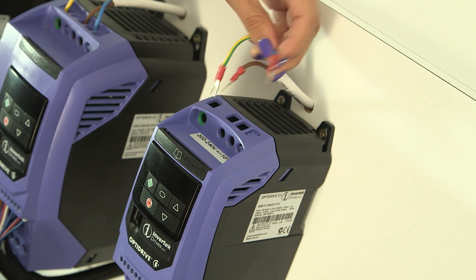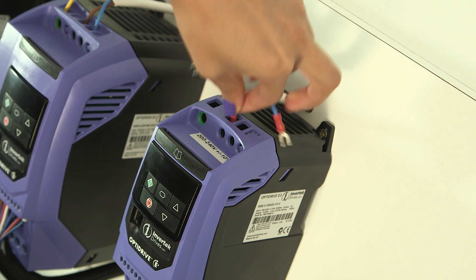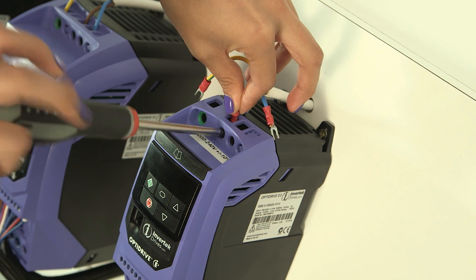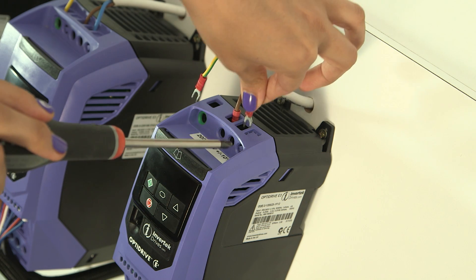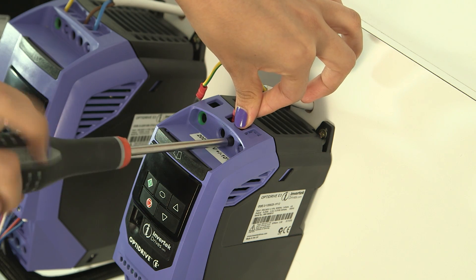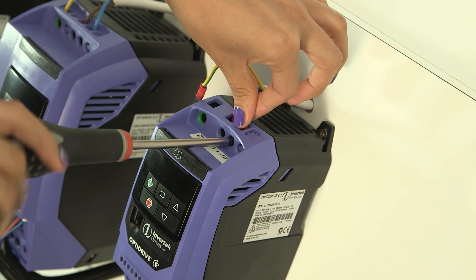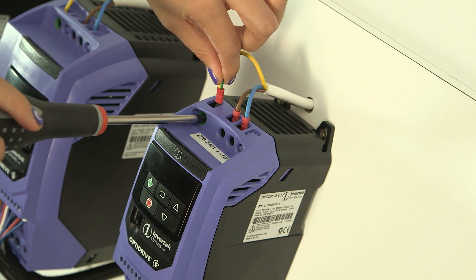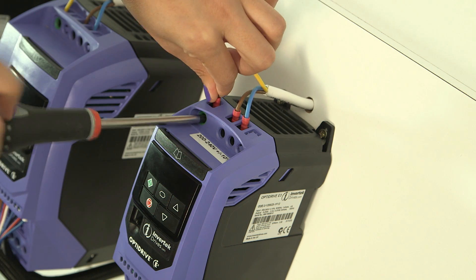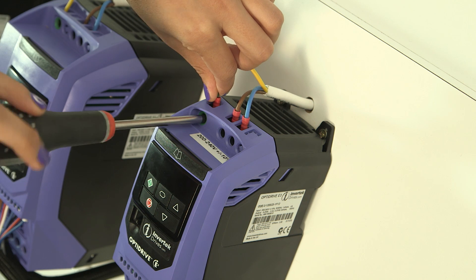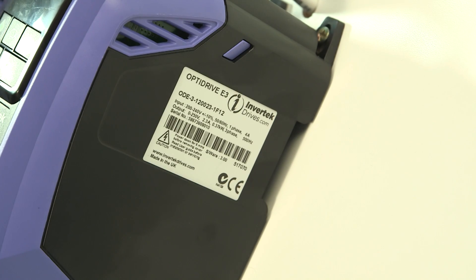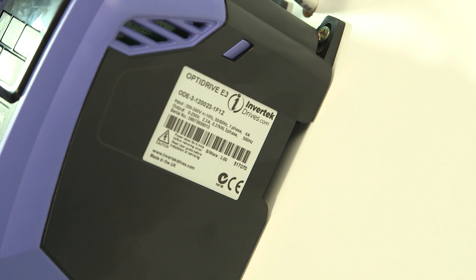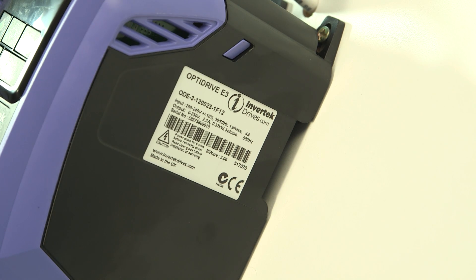Connect L1 and L2 for single-phase supplies. Always connect an earth or ground to the drive, not only for safety, but also for electromagnetic compatibility compliance. The drive will need fusing or similar protection as well. Take a look at the manual for this information.